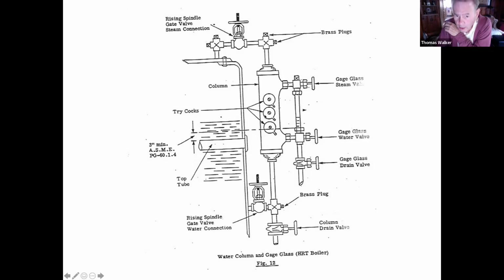Both the water column and the gauge glass are equipped with drain valves called blowdown valves. We're going to blow down the water column and the gauge glass at the start of every watch that we work. That's important. So you're going to do this at the start of every watch.